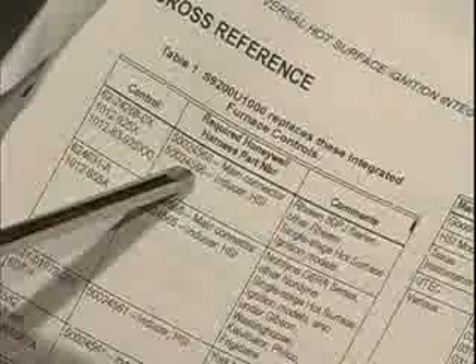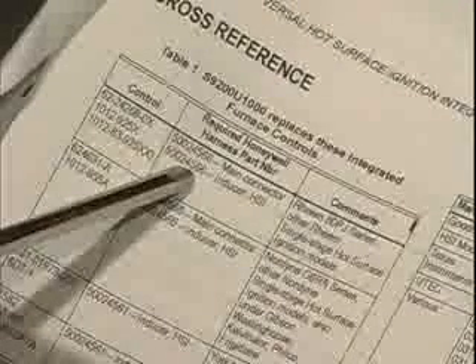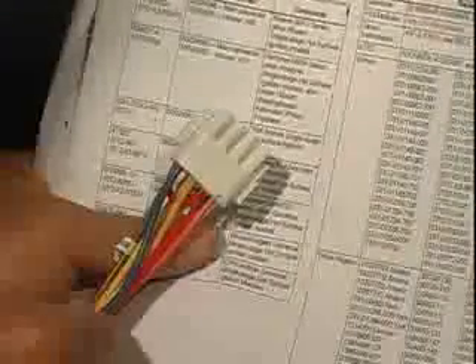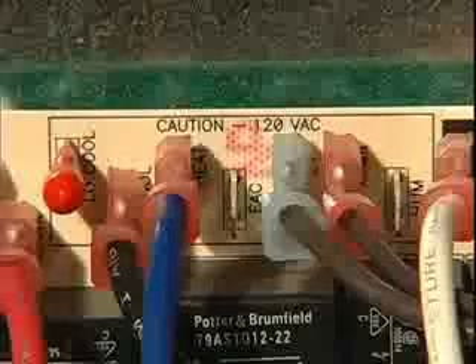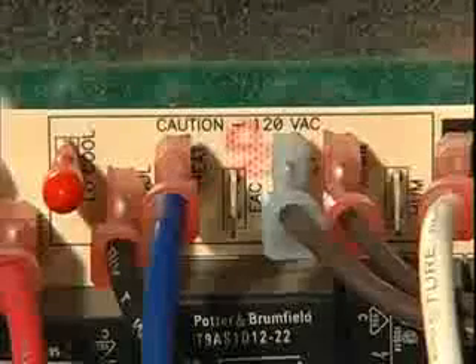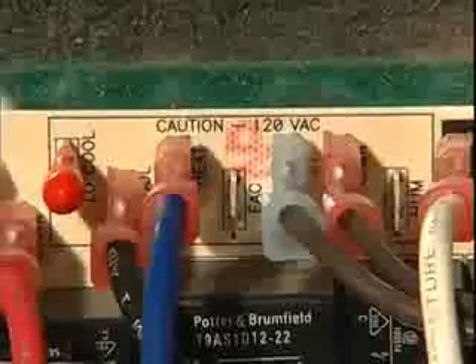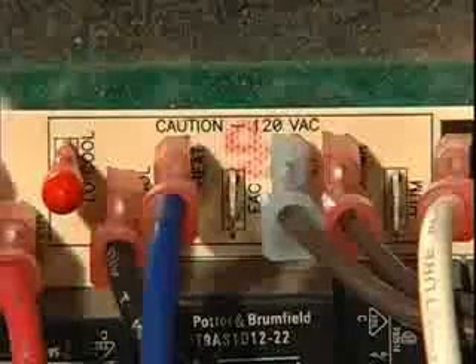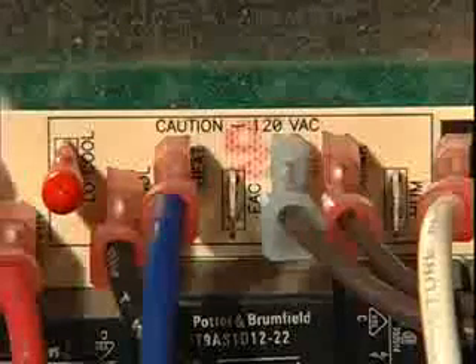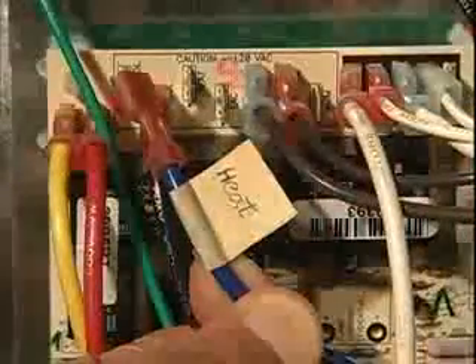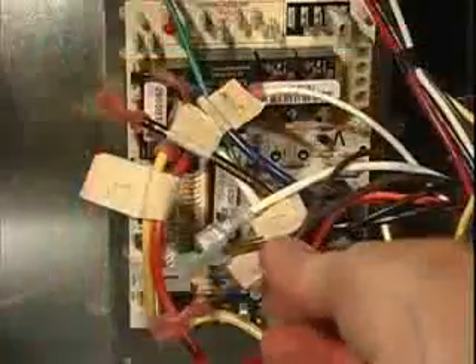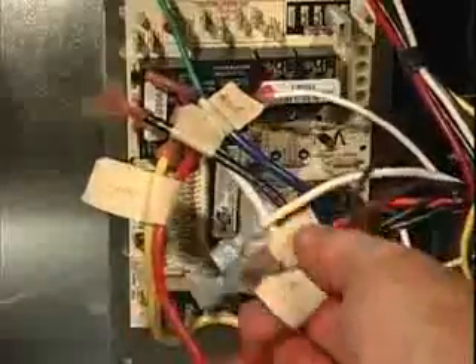The second column in the cross-reference shows which wiring harness to use. In this case, it's the one right here. That gives us a plug-in installation to speed up the job and eliminate the chance of a wiring error. The terminals on the old circuit board are most likely labeled with the name of the load they control, for instance, heat fan, cool fan, and so forth. If they're not, before removing the wires, label them, and you'll save yourself the trouble of tracing all the circuits when you go to put the new board in.